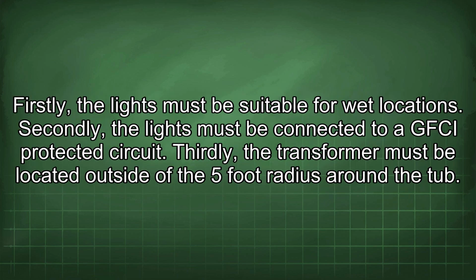Firstly, the lights must be suitable for wet locations. Secondly, the lights must be connected to a GFCI protected circuit. Thirdly, the transformer must be located outside of the 5-foot radius around the tub.